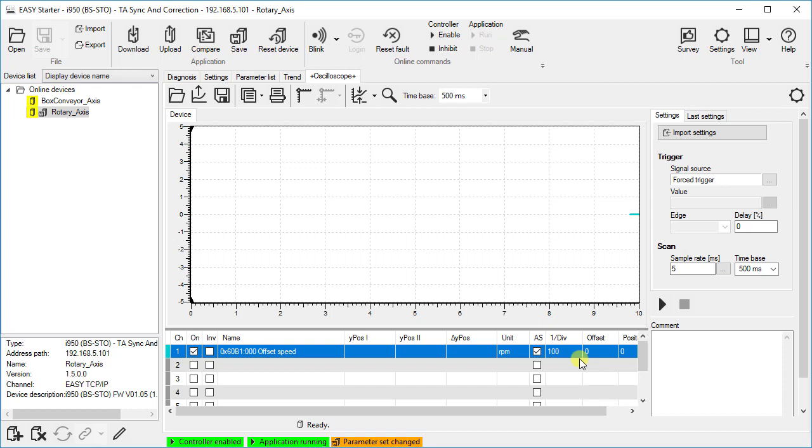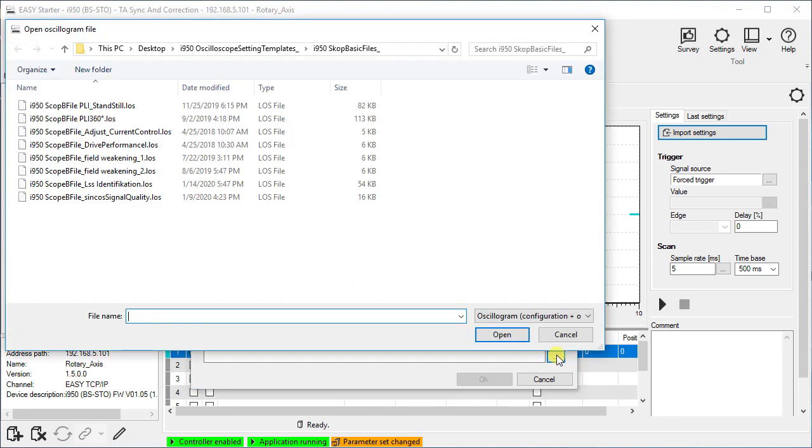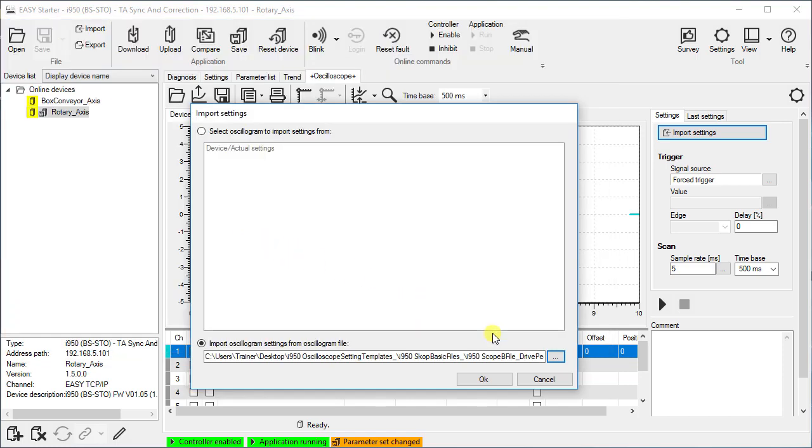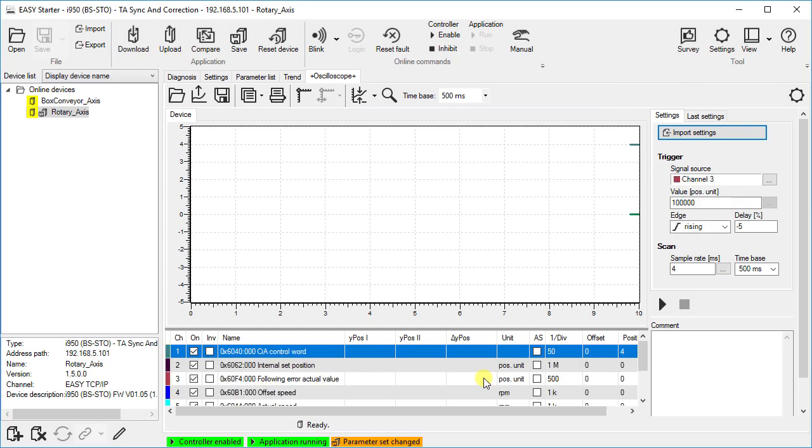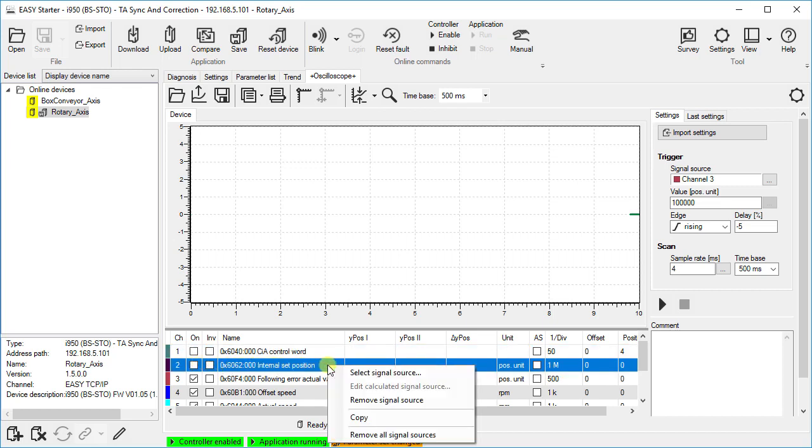Another way to select variables is to import prepared settings. The import function is in the right-hand settings area. By selecting the from file option, all settings can be easily imported from a provided template file. The configuration templates for the i950 inverter can be found on the Lenze website in the knowledge base. We choose the template drive performance for our oscilloscope recording. Afterwards, we can adapt the pre-selected variables to our requirements. For example, unused channels can be switched off or completely removed from the channel list.